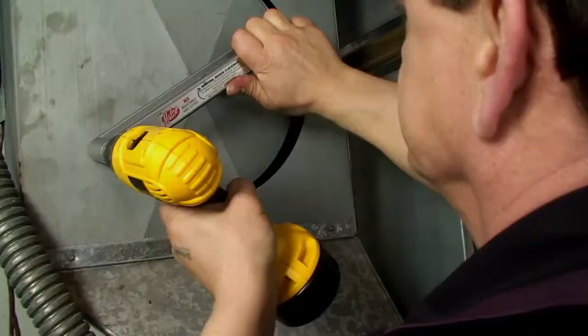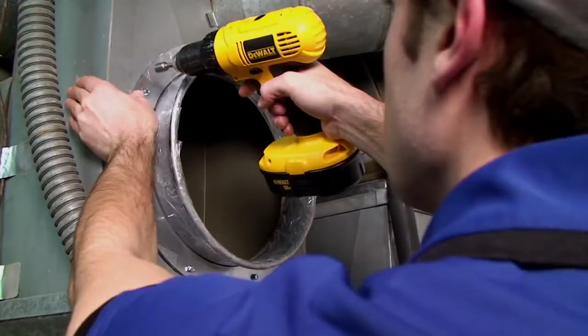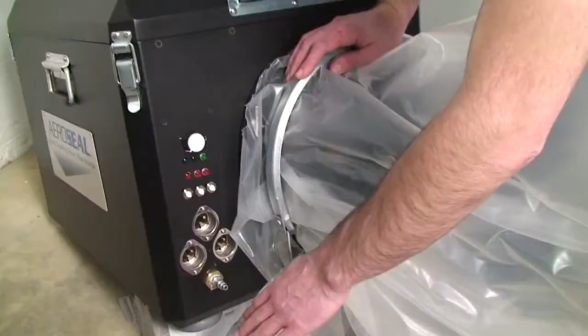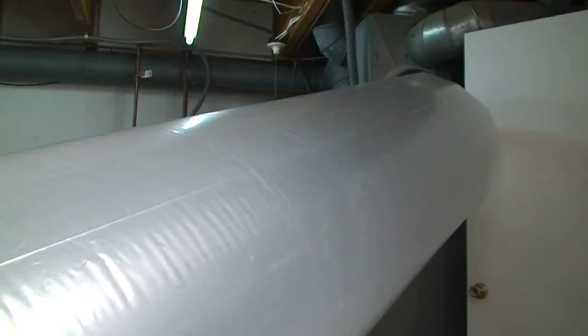First, a technician will install foam plugs into all air duct openings. An access hole is cut into the supply or return plenum, and a temporary collar is attached. The Aeroseal injection machine is then connected to the duct system using a long, flexible plastic tube. A patented computer-controlled injection machine heats up adhesive particles suspended in a liquid. As the particles are heated, they dry up and become suspended in air. A fan blows these small, dry adhesive particles into the temporarily blocked duct system.